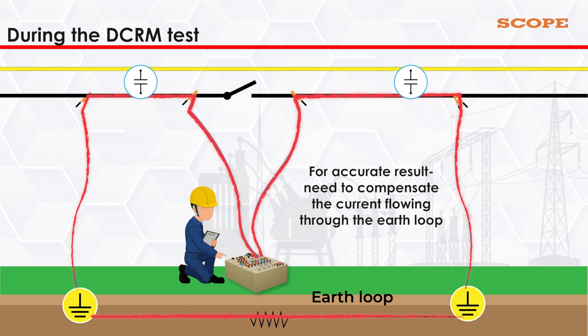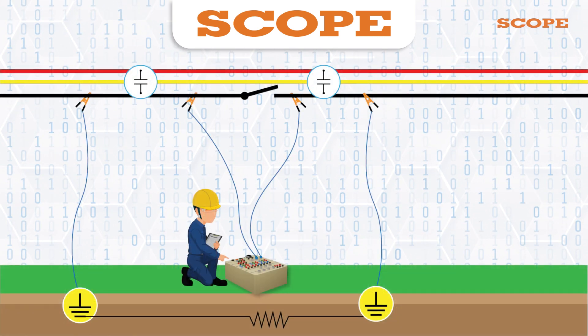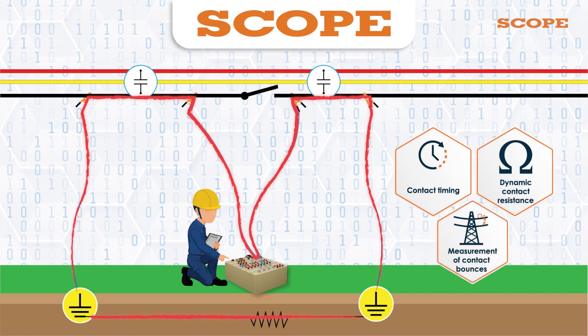To get the accurate result, we need to compensate the current flowing through the earth loop. Scope has developed and implemented special technology and algorithms to dynamically measure and compensate the current flowing through the earth loop and get the correct results of contact timings and dynamic contact resistance while the circuit breaker is grounded from both sides. Measurement of contact bounces has also become possible with this method.